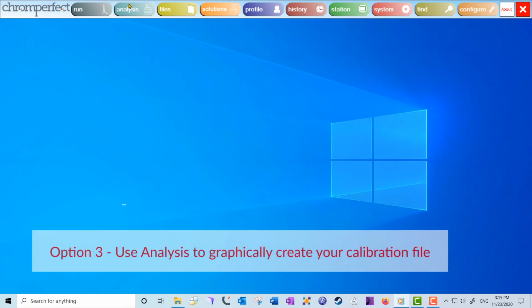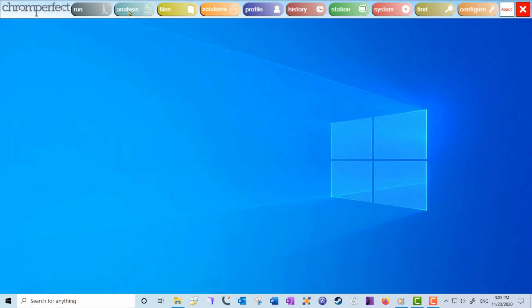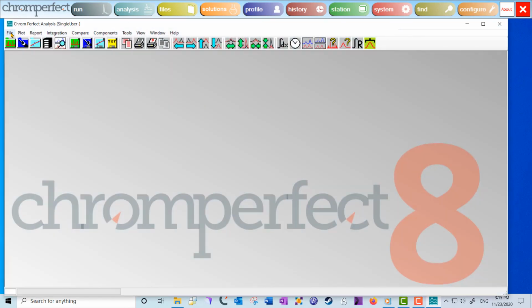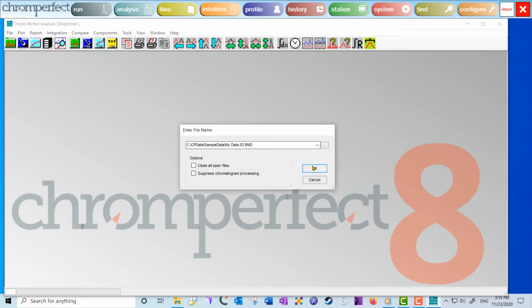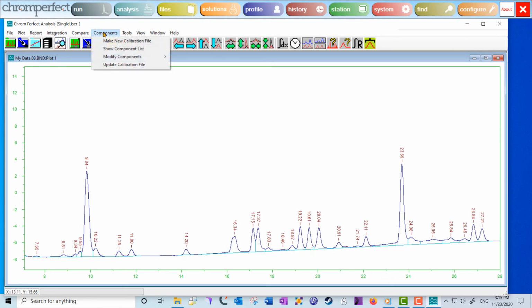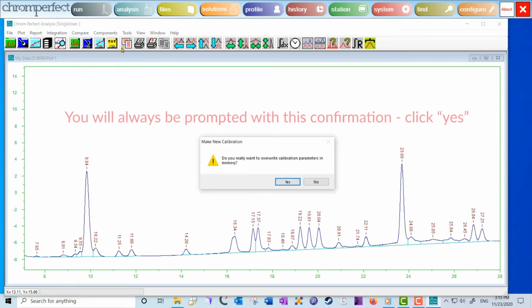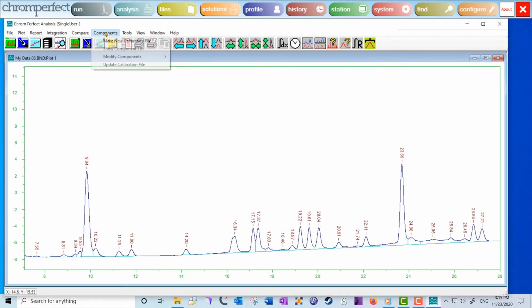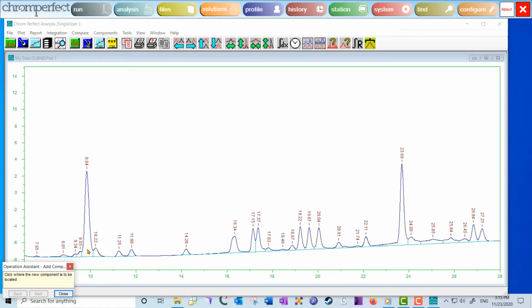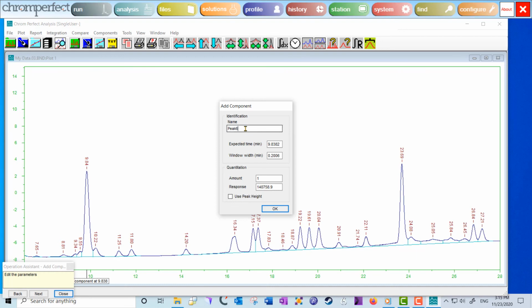The third option for creating a calibration file is to use the graphical capabilities of the analysis program and then finalize it in the file editor. Within the analysis program, open your recent chromatogram. Select the Components menu item. Select Make New Calibration File. Then modify Components and Add. Left-click on the peak of interest and right-click to confirm.